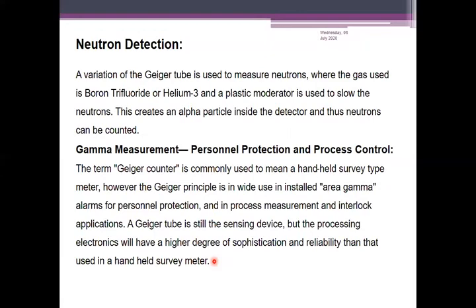For neutron detection, a variation of the Geiger-Müller tube is used where the gas is boron trifluoride or helium-3 and a plastic moderator is used to slow the neutrons. This creates an alpha particle inside the detector, allowing neutrons to be counted. For gamma measurement, personal protection, and process control, the Geiger counter principle is also applied in installed-area gamma alarms and process measurement and interlock applications, where the Geiger tube remains the sensitive device with high-specification processing electronics.